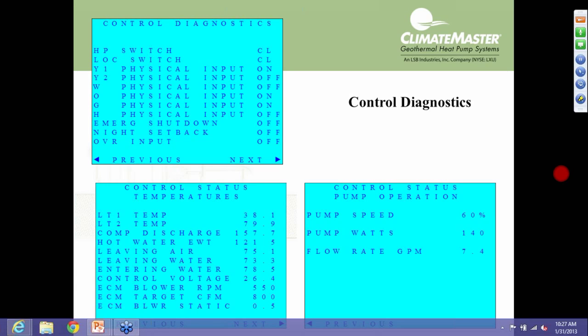Then the third screen is your pump screen. There you'll see your pump speed and percentage. So again, in manual operation, we would drive that up until we would go into this screen and see the flow rate that we wanted to see. You can also see your pump watts. Again, that's where this pump really shines, as I mentioned earlier in the presentation. Pump watts are a whole lot lower with these variable speed pumps than your typical single speed pumps that we've used for years out there.